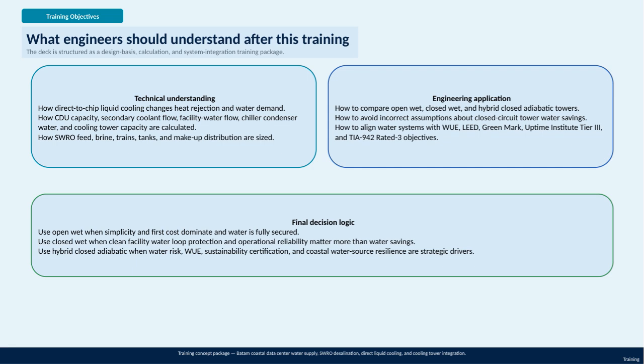Finally, we'll provide clear decision-making guidance for choosing the appropriate cooling tower type based on specific priorities. If simplicity and initial cost are critical and water availability is secure, open wet towers are preferred. However, if protecting the facility's clean water loop and ensuring operational reliability are paramount, closed wet towers are the better choice.